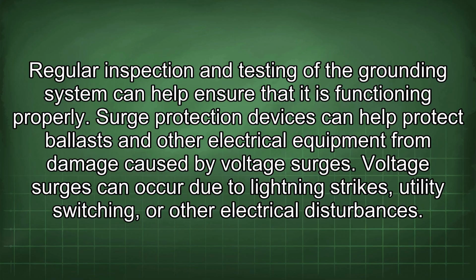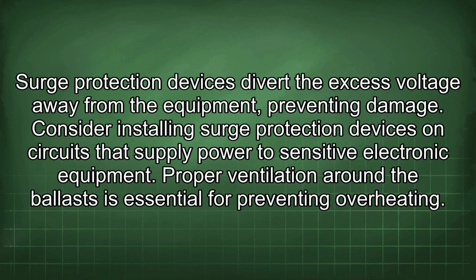Surge protection devices can help protect ballasts and other electrical equipment from damage caused by voltage surges. Voltage surges can occur due to lightning strikes, utility switching, or other electrical disturbances. Surge protection devices divert the excess voltage away from the equipment, preventing damage. Consider installing surge protection devices on circuits that supply power to sensitive electronic equipment.